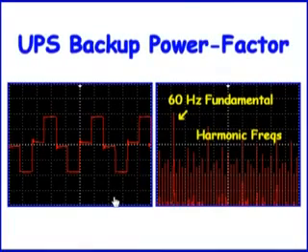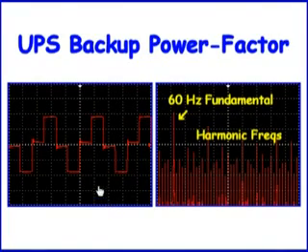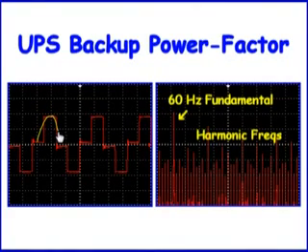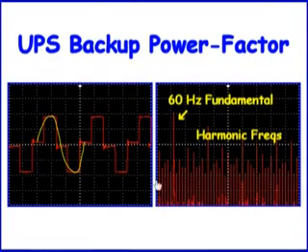Here's the pseudo sine wave from an uninterruptible power supply during an electrical outage when the UPS is on battery backup. Notice the distorted AC sine wave — it's like it's built from a bunch of square waves. By distorting the AC sine wave, harmonic currents are produced, and this is what causes the low power factor in a UPS backup.